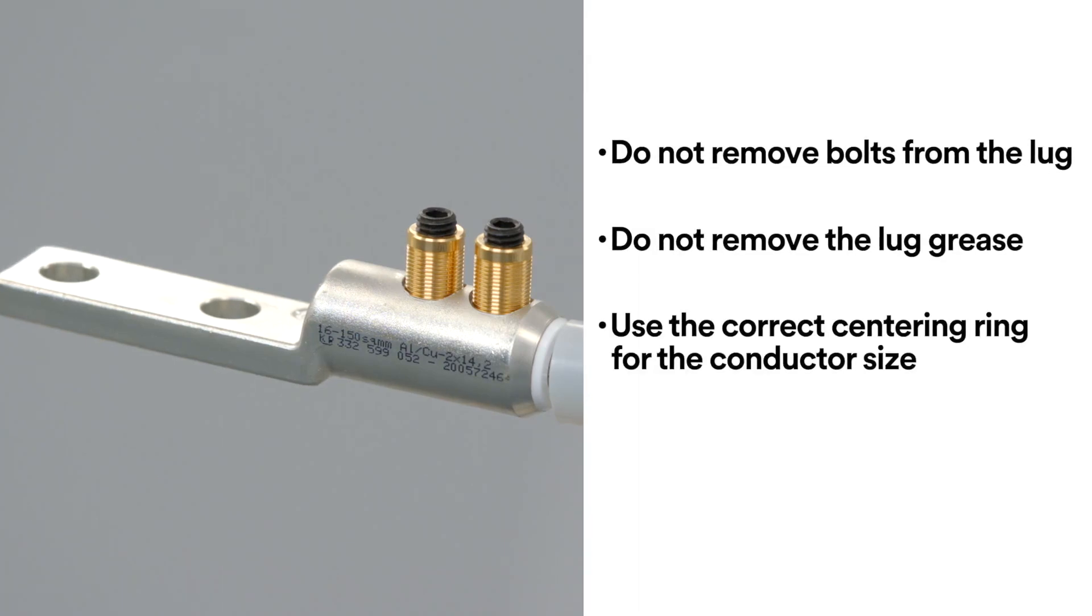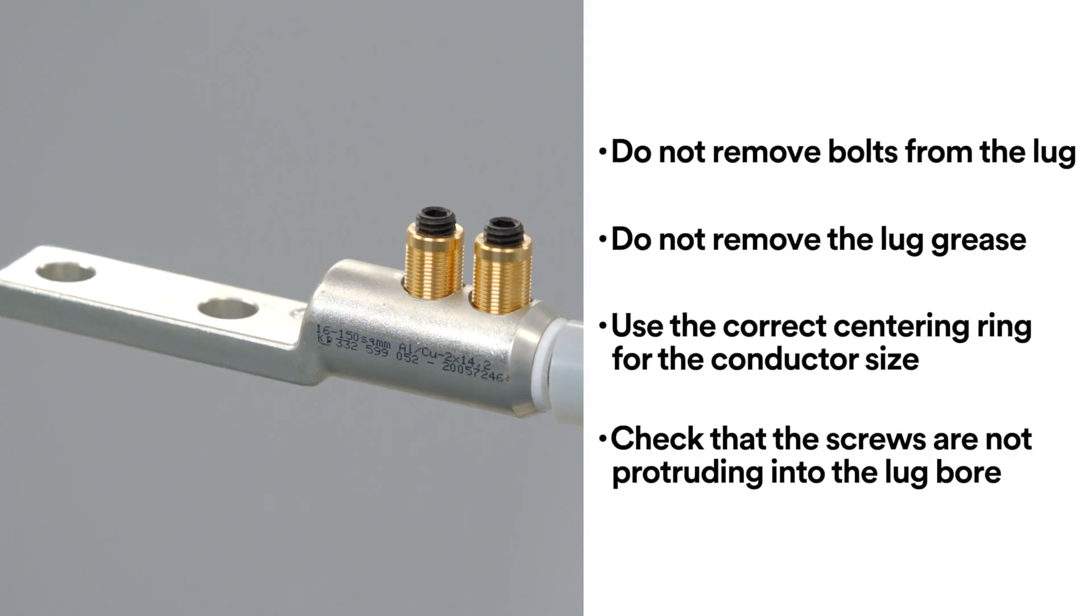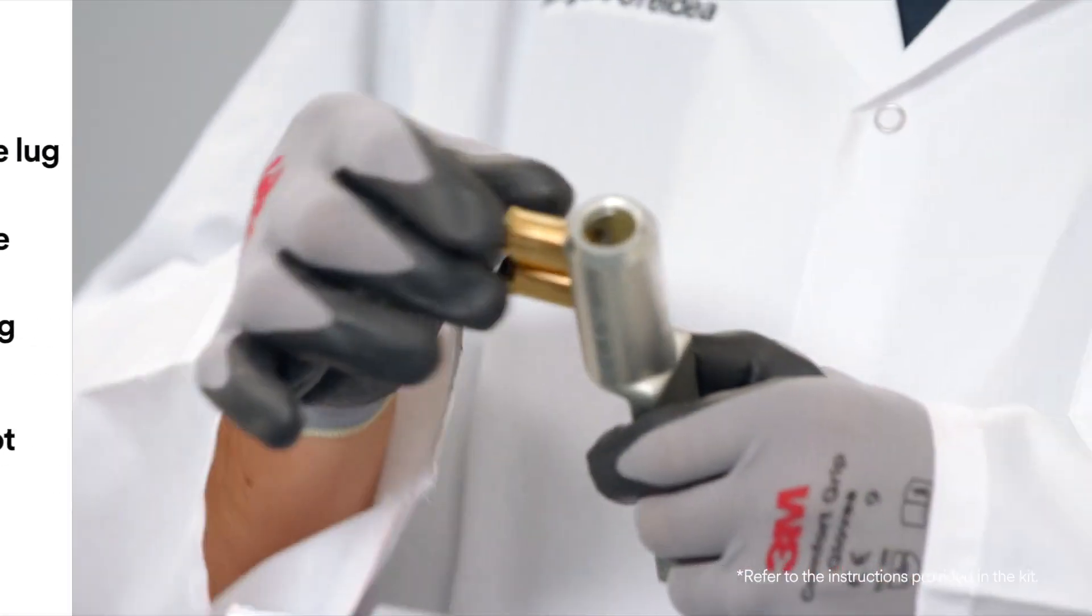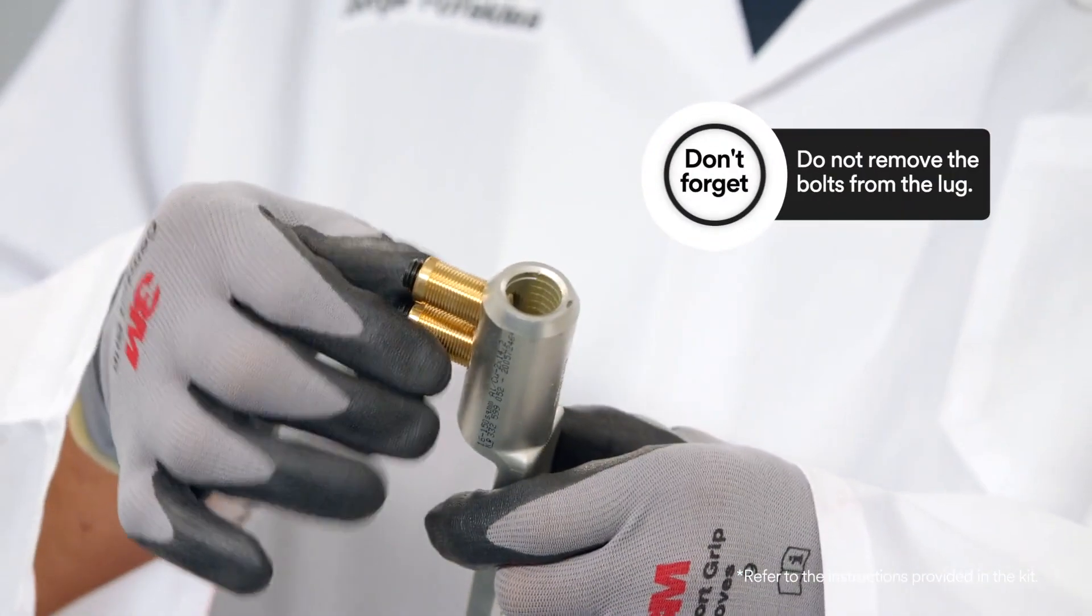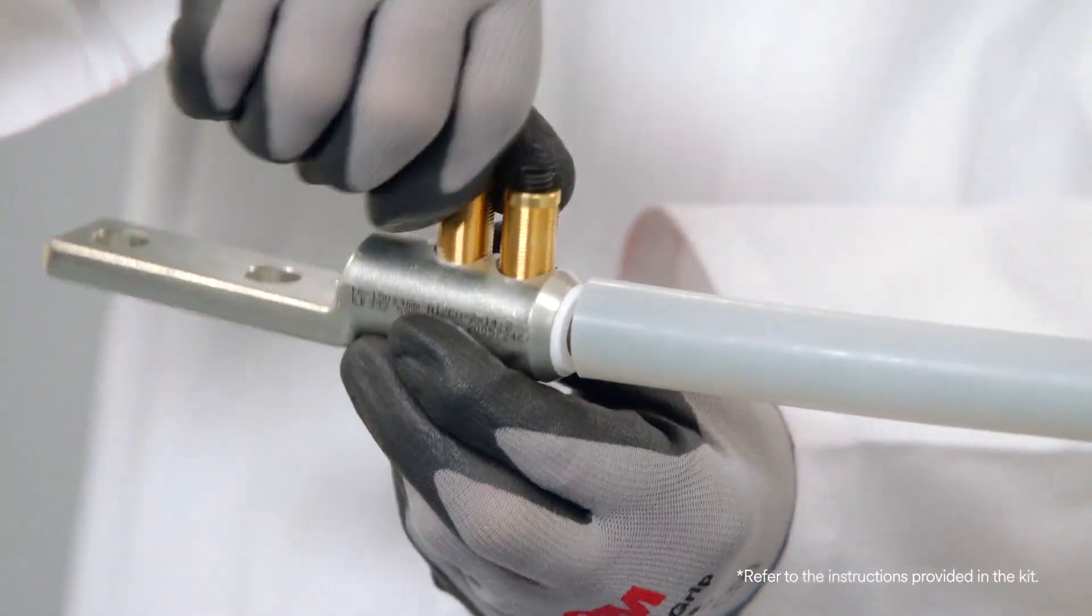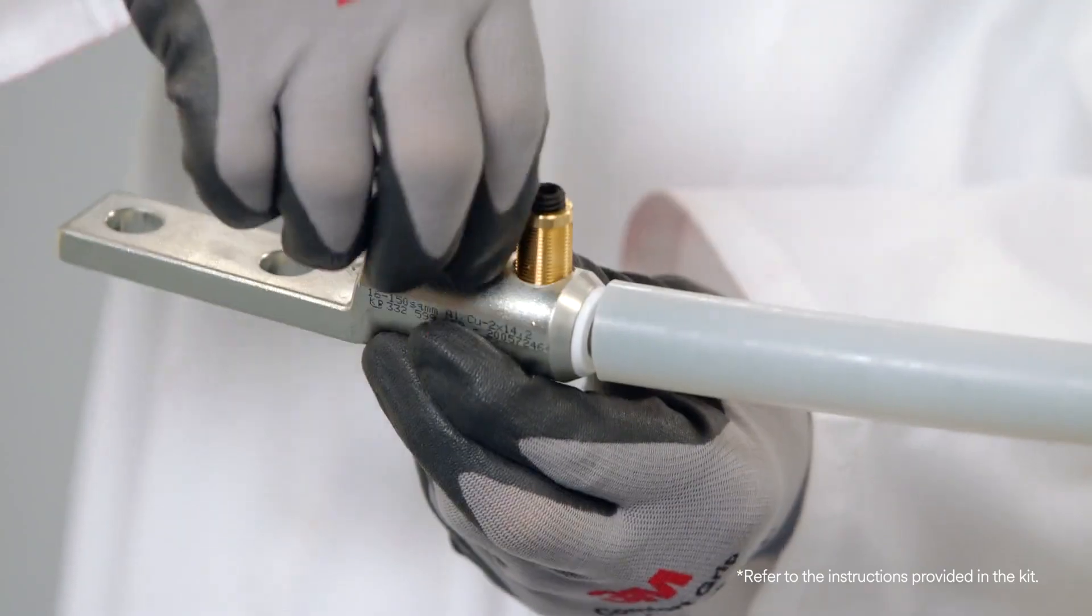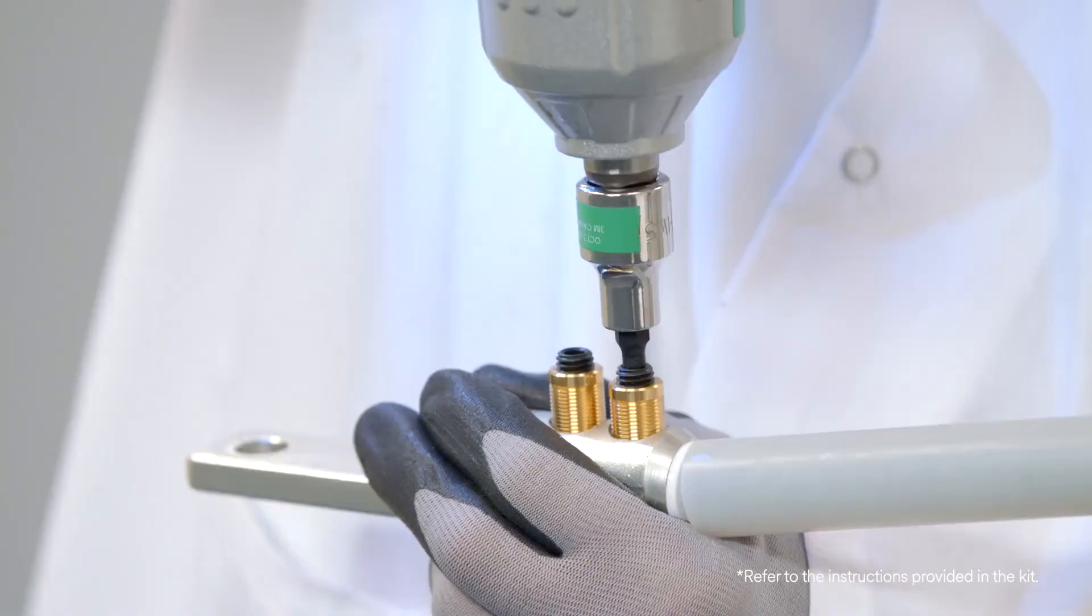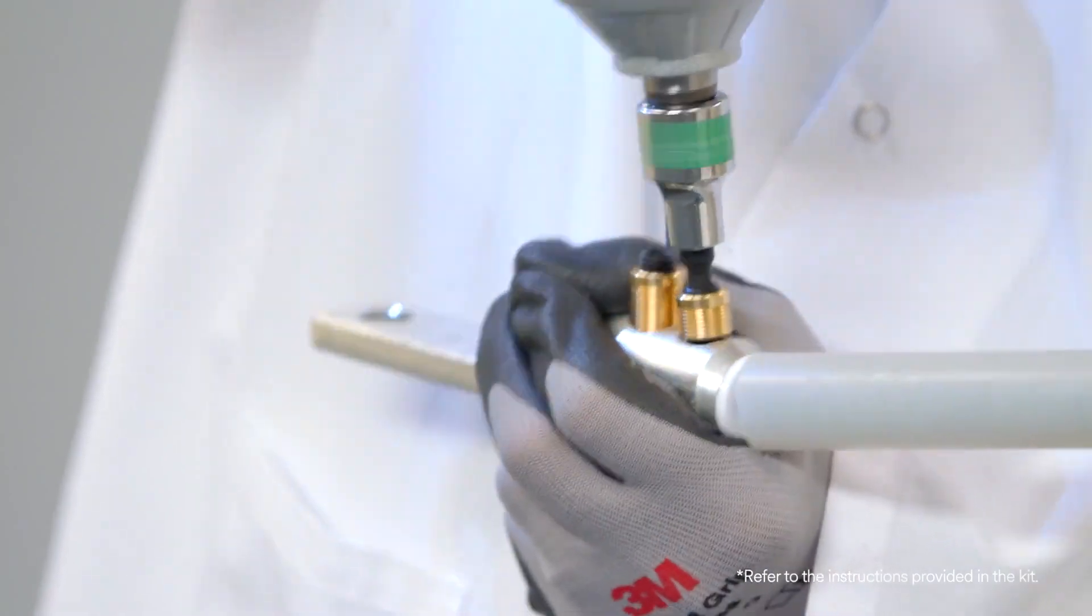Make sure that you use the correct centering ring for the conductor size. You also need to check that the screws are not protruding into the lug bore. Once you've done these checks it's time to install the lug. Follow by hand tightening all bolts into the conductor. Shear the bolts.